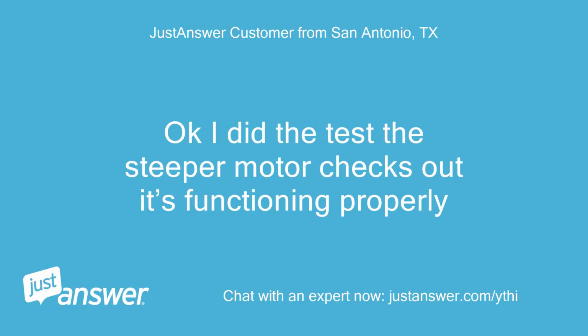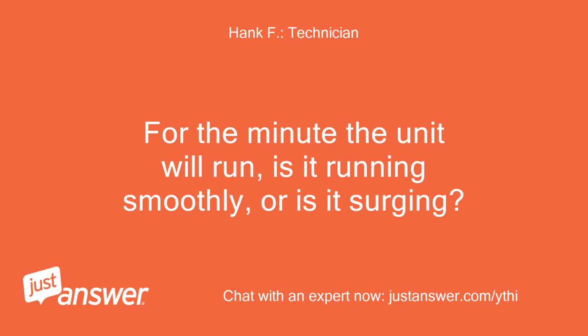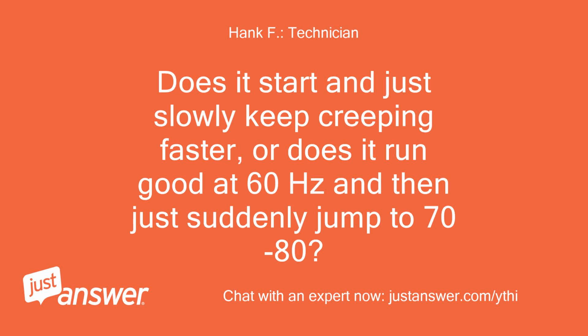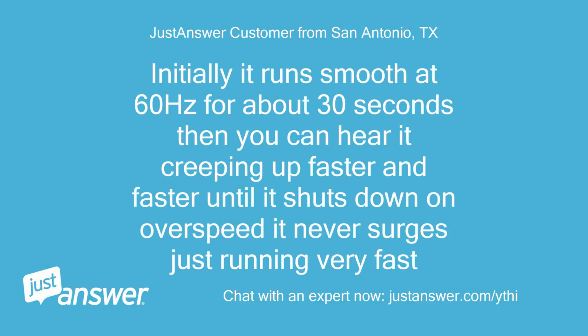Okay, I did the test. The stepper motor checks out, it's functioning properly. For the minute the unit will run, is it running smoothly, or is it surging? Does it start and just slowly keep creeping faster, or does it run good at 60 Hz and then suddenly jump to 70-80? Initially it runs smooth at 60 Hz for about 30 seconds, then you can hear it creeping up faster and faster until it shuts down on overspeed. It never surges, just running very fast.